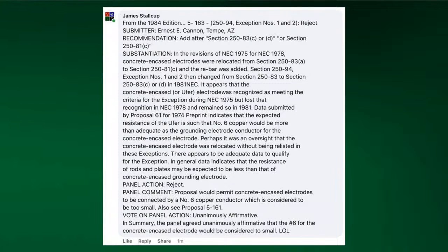Well, okay. Yeah, and it's considered too small based on the testing, right? That's right. That's the data that was submitted. And so you're saying that those Ufer electrodes were tested with those size conductors and not just all tested with number 8 and said it was adequate? Yeah, they said it had to be that size to be adequate. And that's what gets me, because he states that the number 6 would be more than adequate, but yet he wants to go lower. That makes no sense.